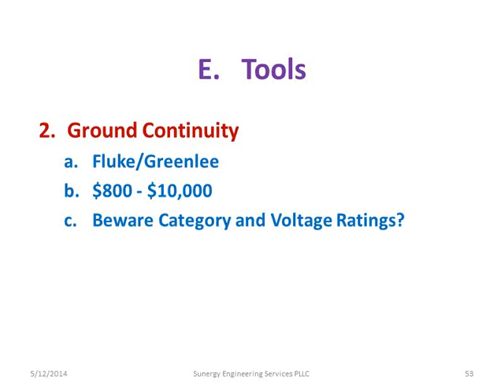And the other problem is the category and voltage ratings on some of these are not very high, because a lot of the cheaper ones are made for 240 volt systems. So if you're testing a 600 volt DC system, it's not exactly appropriate.